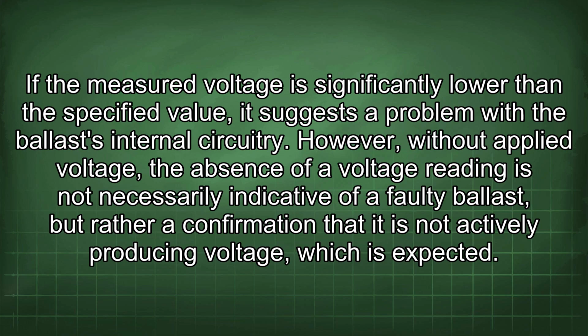If the measured voltage is significantly lower than the specified value, it suggests a problem with the ballast's internal circuitry. However, without applied voltage, the absence of a voltage reading is not necessarily indicative of a faulty ballast, but rather a confirmation that it is not actively producing voltage, which is expected.